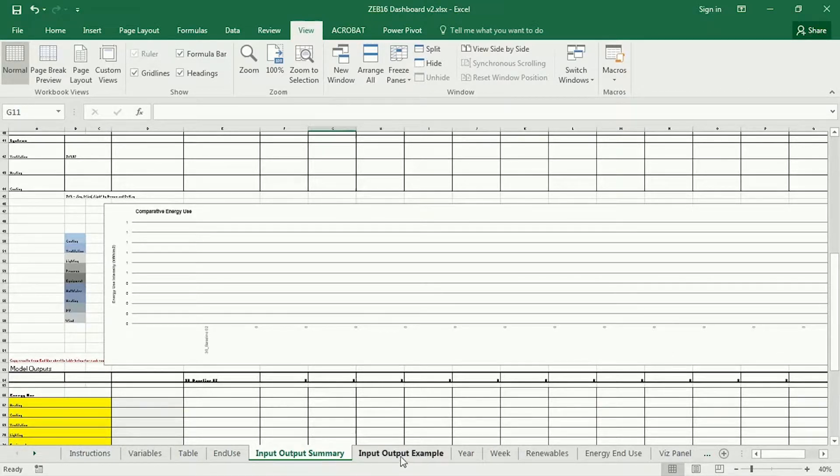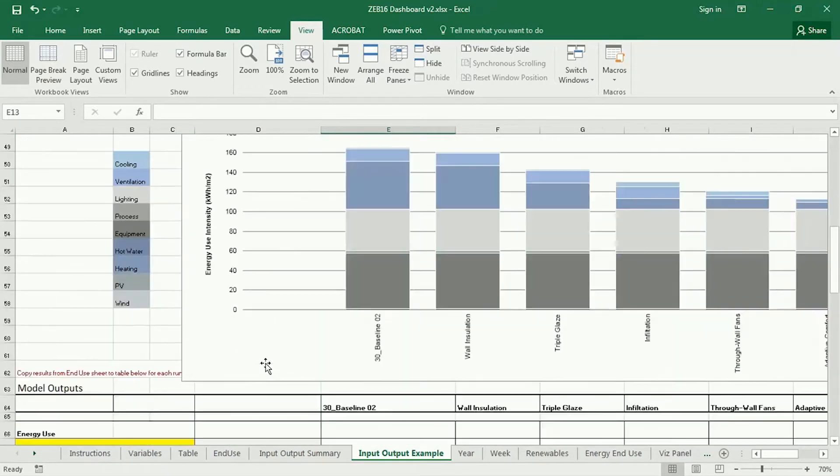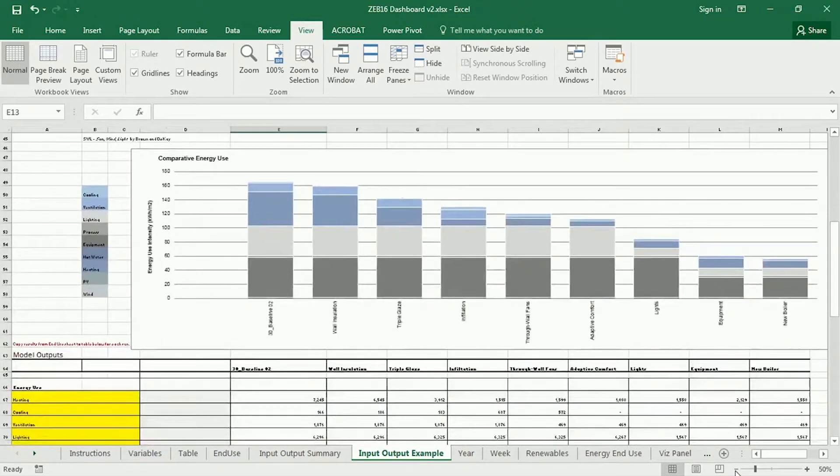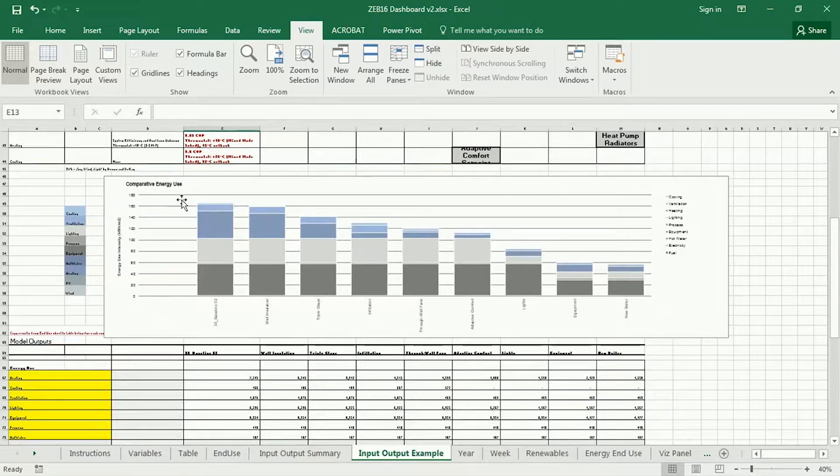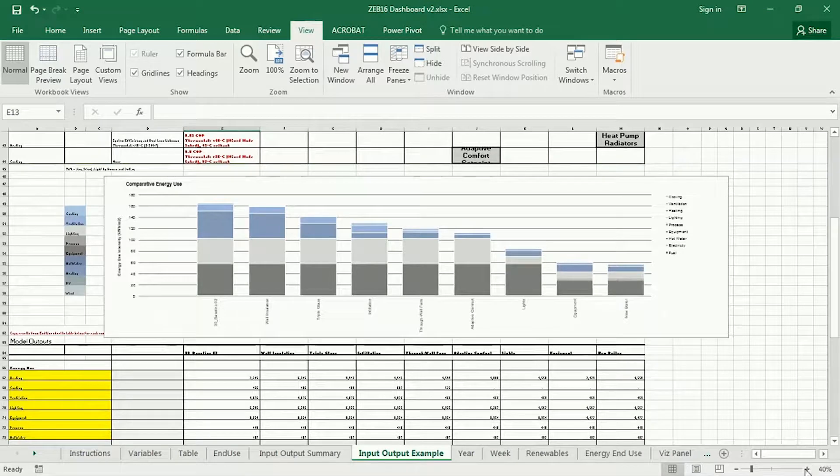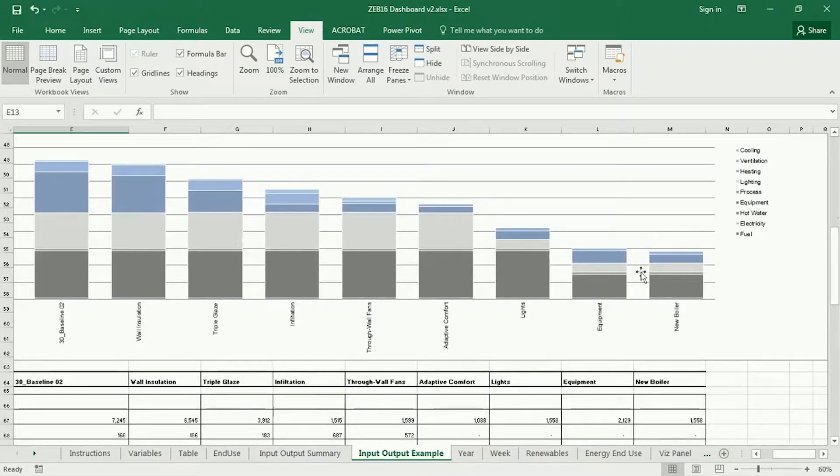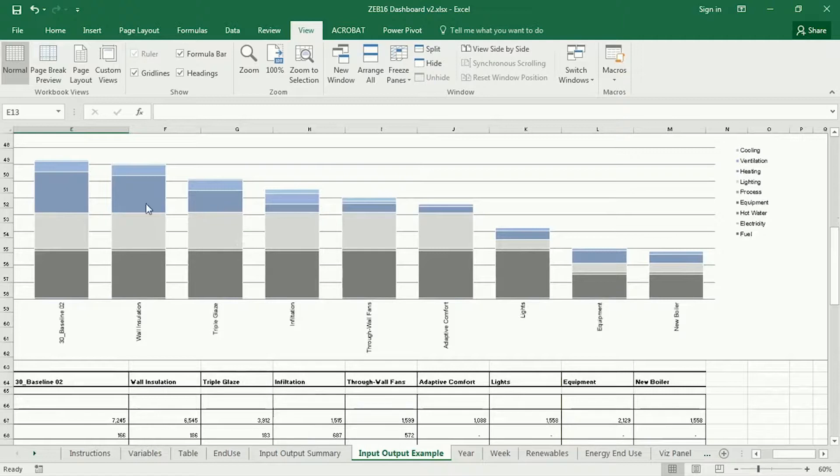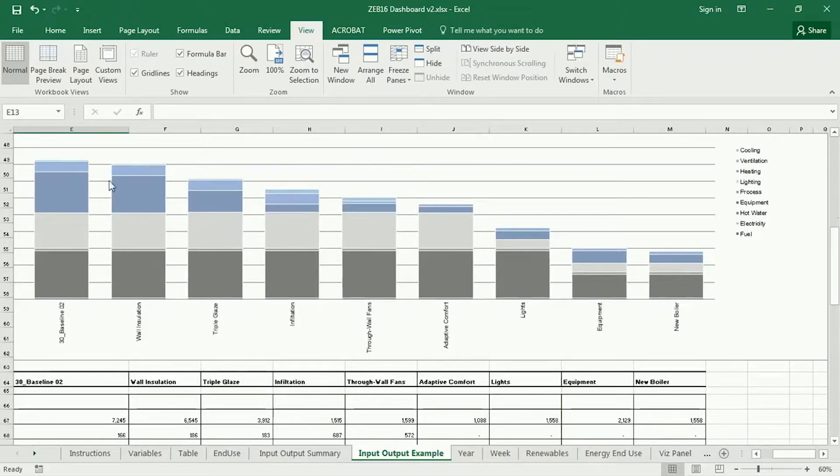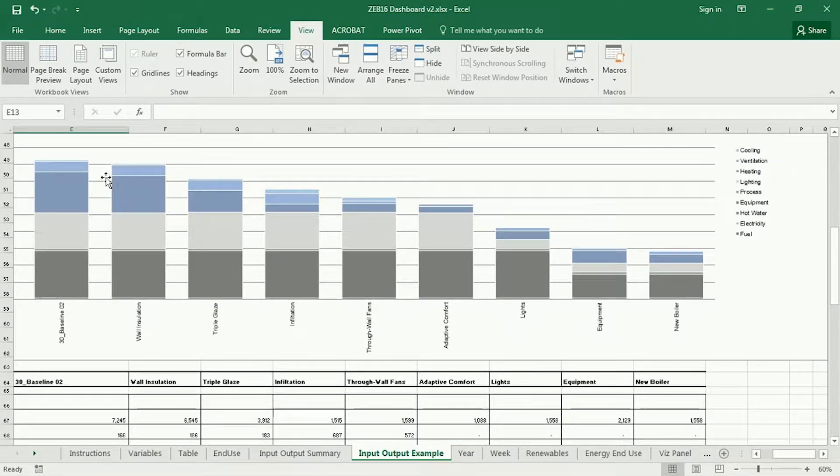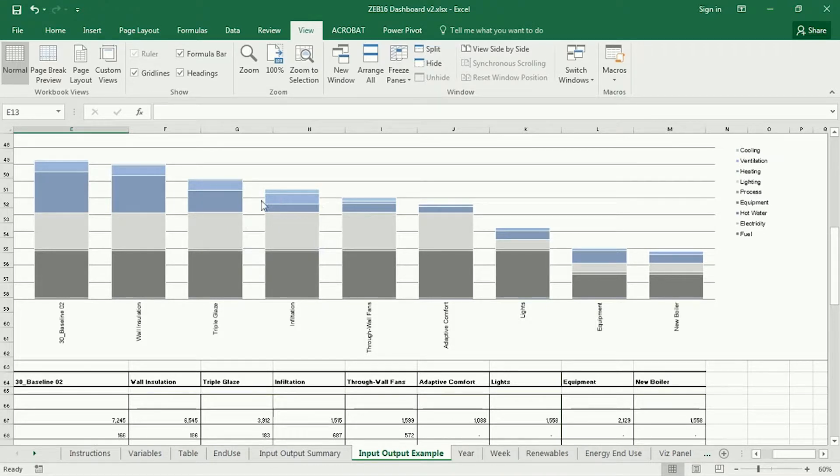And I've gone ahead and run all this. And just like the cooking shows, an hour later, we've got this nice progression of energy efficient measures as they go from the baseline to insulation to glazing, so on and so forth. And then this one over here would represent the entire suite because these are all cumulative. Interestingly enough, you can see that this wall insulation, which was my first thing to make my thermos, had some effect. It changed, it reduced the heating a fair amount, but not a huge effect, which is surprising. You can see that the triple glazing made much more of a difference and the infiltration made even more of a difference.